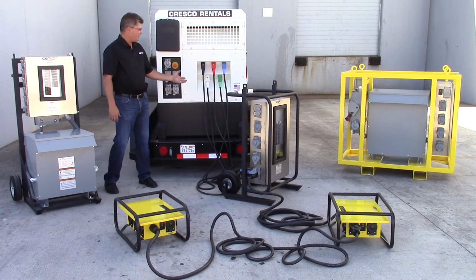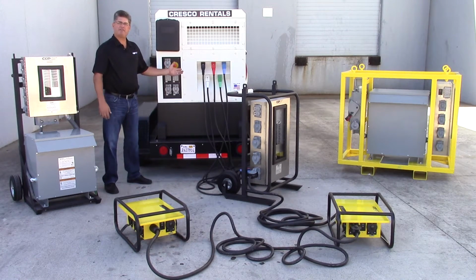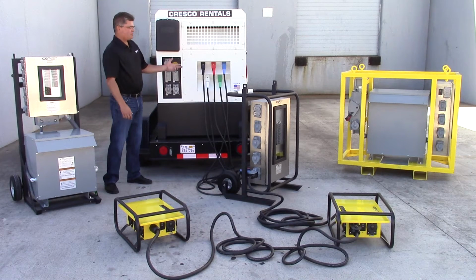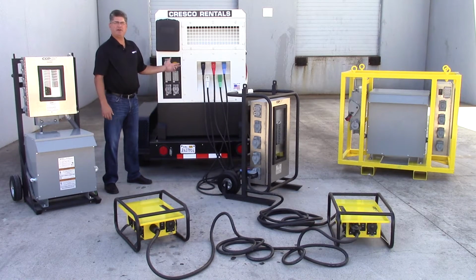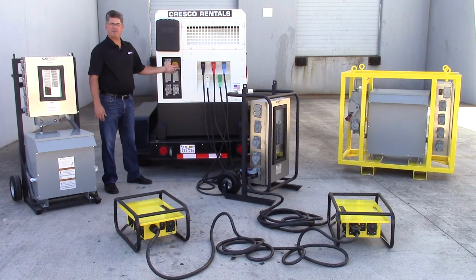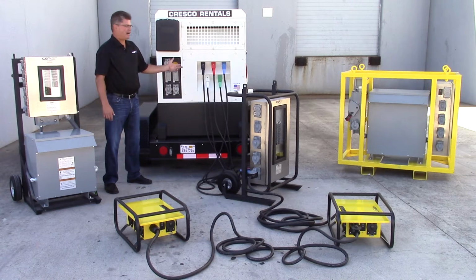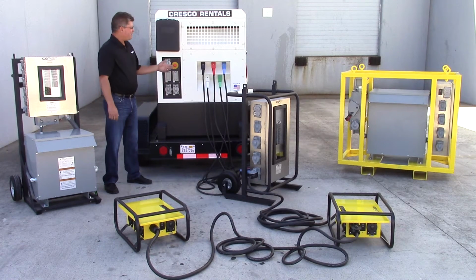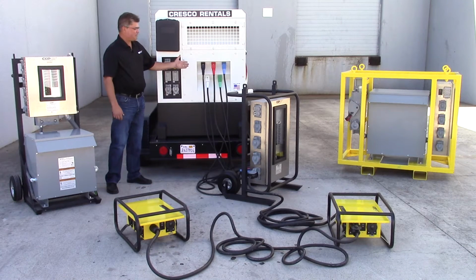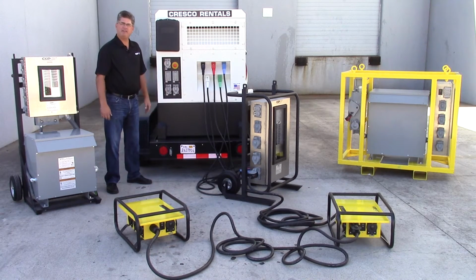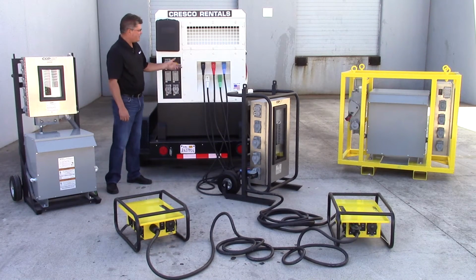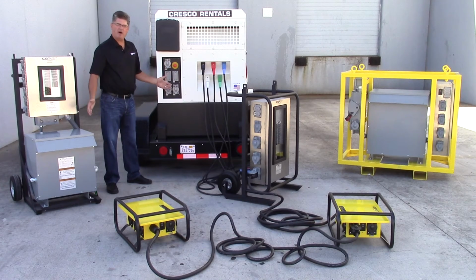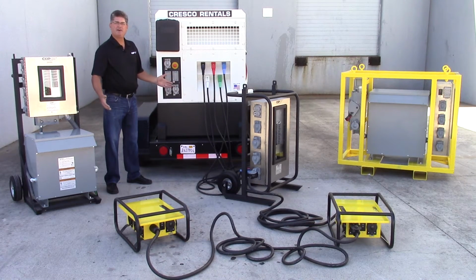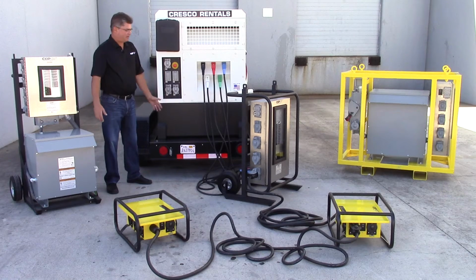First, I want to start by talking about the 3-phase aspects of these larger generators. In order to really maximize the output of this generator, you need to utilize the 3-phase selector or the 3-phase voltage allowable on this unit. This particular unit came already pre-assembled with cam locks, which makes it very convenient and easy for a user to plug and play right into the system without having to wire any pigtails to the main lugs or do any type of hard wiring themselves.